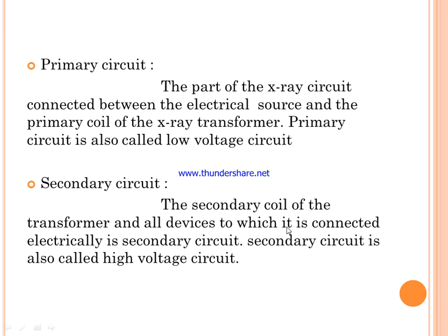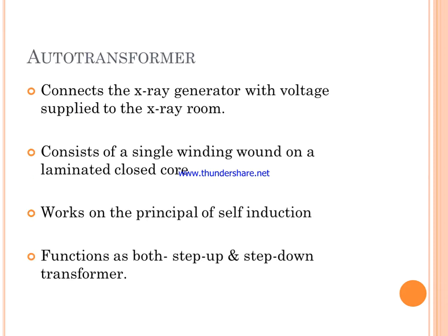The secondary circuit is also called the high voltage circuit. The auto transformer connects the X-ray generator with the voltage supplied to the X-ray room. It consists of a single winding wound on a laminated closed core and works on the principle of self-induction.